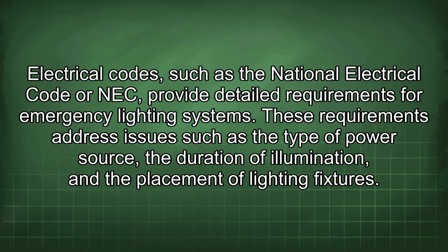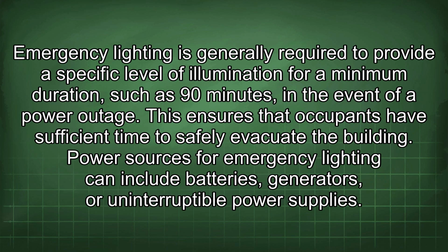Electrical codes, such as the National Electrical Code or NEC, provide detailed requirements for emergency lighting systems. These requirements address issues such as the type of power source, the duration of illumination, and the placement of lighting fixtures. Emergency lighting is generally required to provide a specific level of illumination for a minimum duration, such as 90 minutes, in the event of a power outage. This ensures that occupants have sufficient time to safely evacuate the building.